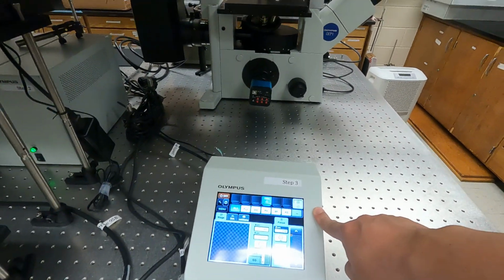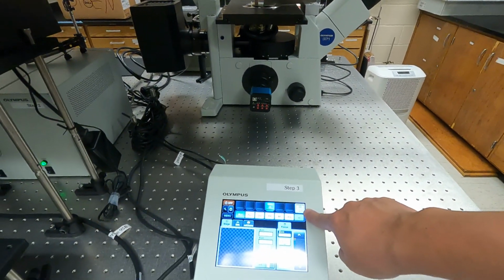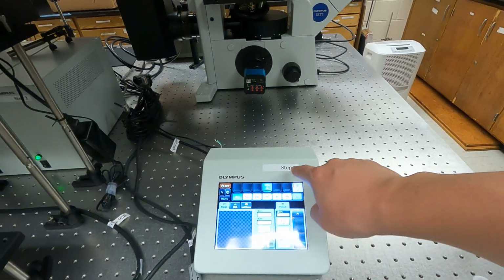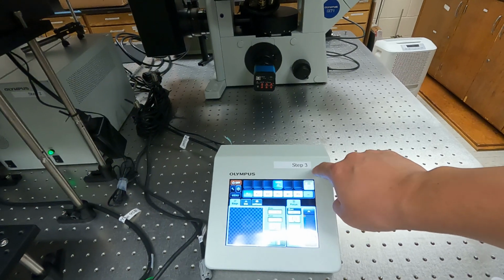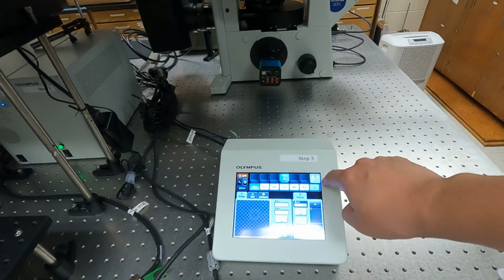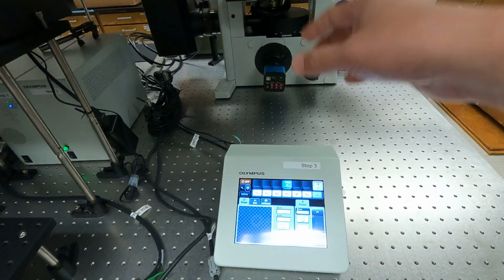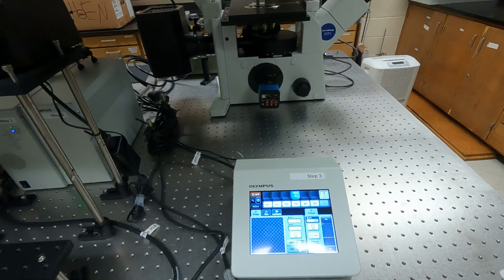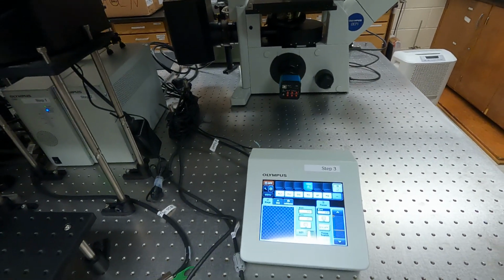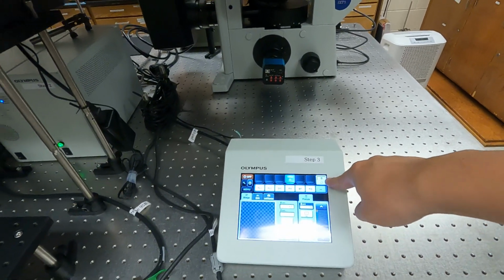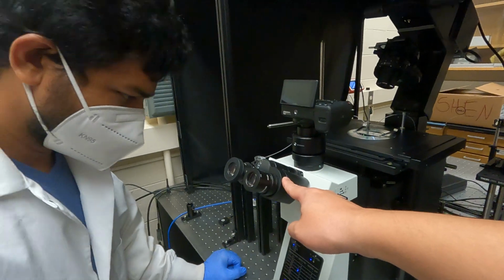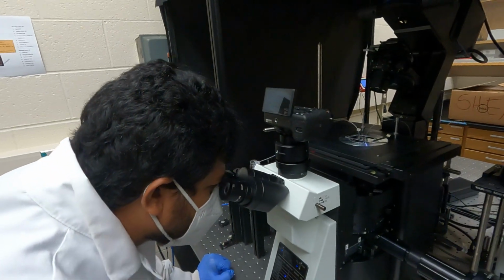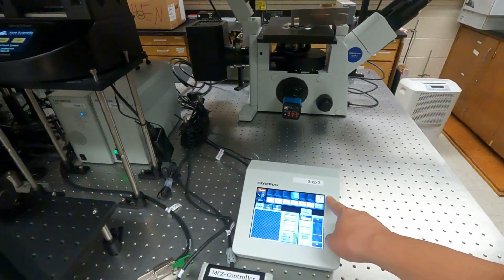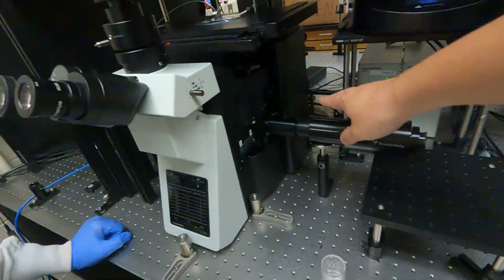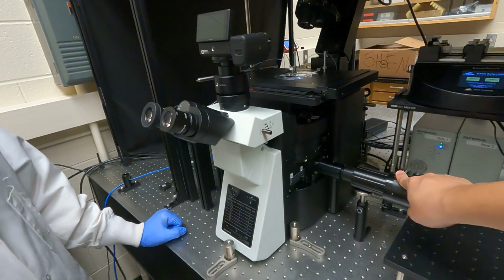There are a few other things we need to pay attention to on this console. The most important thing is to check the icon on the top right corner of this entire screen. This controls the internal mirror selection of the microscope body. If you click it, you will hear a motor sound inside the microscope body. That means the internal mirror is rotating. When you see an icon that shows an eye, all the light is redirected into the eyepiece. You'll be able to view the image through the eyepiece. Under this mode, none of these two ports will sense any of the light. All of the light will be redirected into the eyepiece.